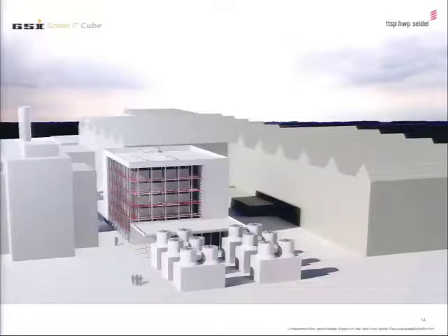The trick is it's just plain physics, because evaporating water gives a large delta T. So even if the outside temperature is 32, 33 degrees, which we reached this summer in Darmstadt, the cooling water is something like 26, 27 degrees, due to the evaporation cooling of the waterfall. Inside these cabinets we have special water-cooled cabinets of a special design, and a delta T of about 1 degree or less is sufficient to cool down.